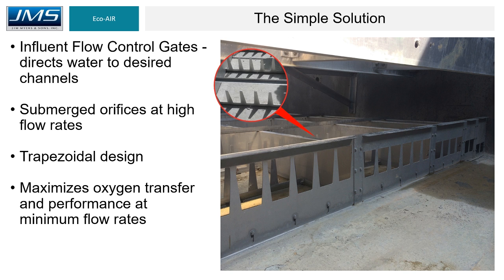Here you can see the influent flow control gates, trapezoidal in shape, located at the influent of the LPCA. There is an influent chamber where, as water rises, it is directed into the respective channel for maximum oxygen transfer at that respective flow rate. The trapezoidal shaped finger weirs allow for maximum oxygen transfer and performance at minimum flow rates and across the full range of daily flow.